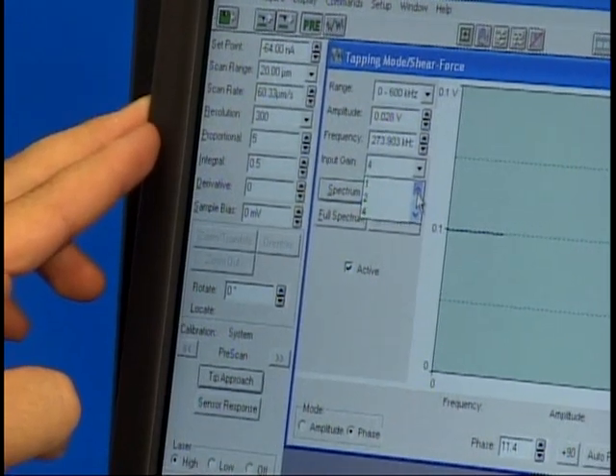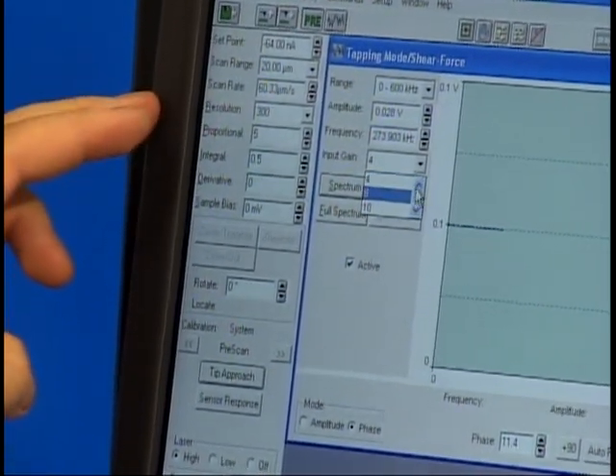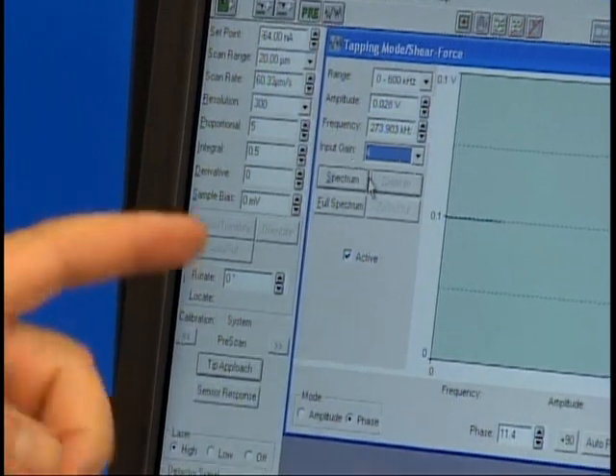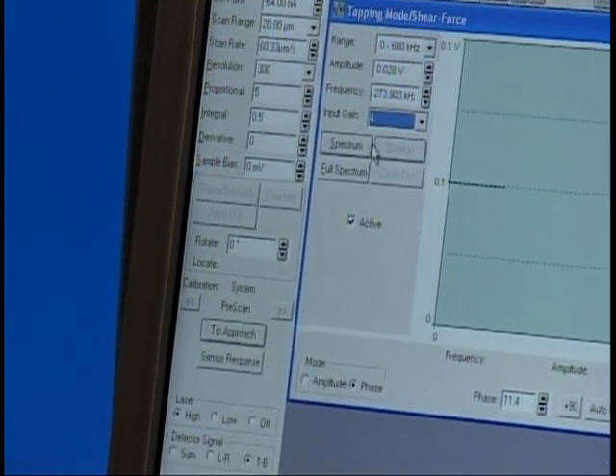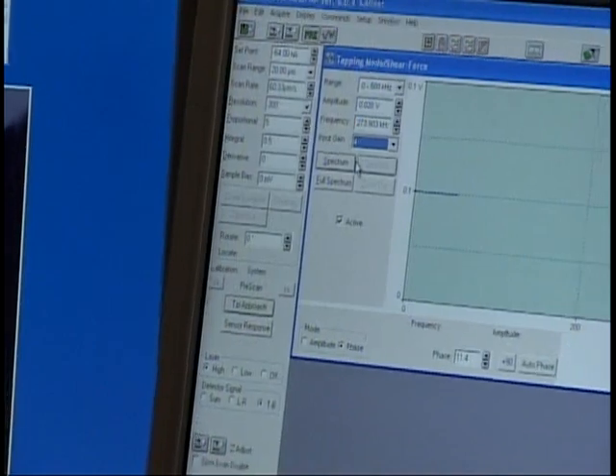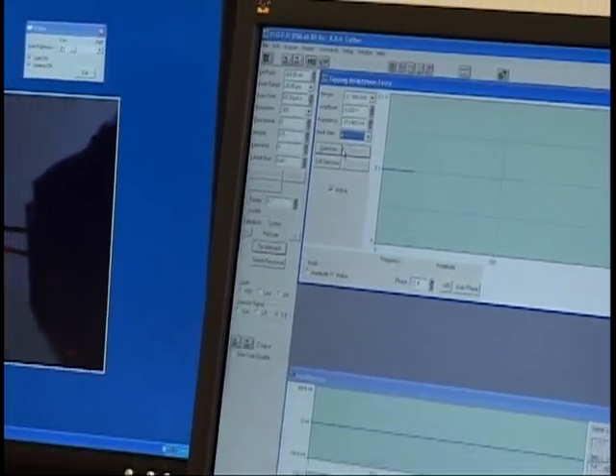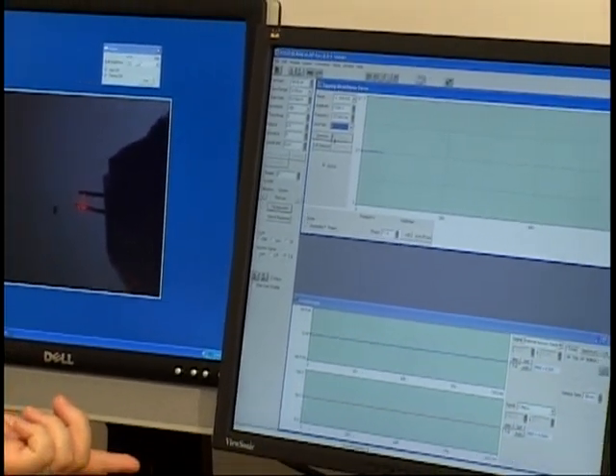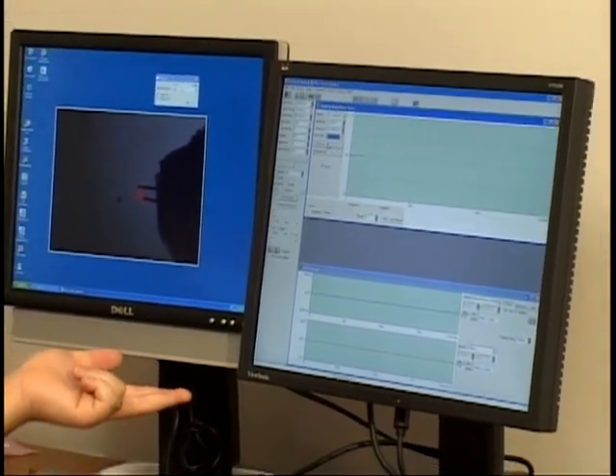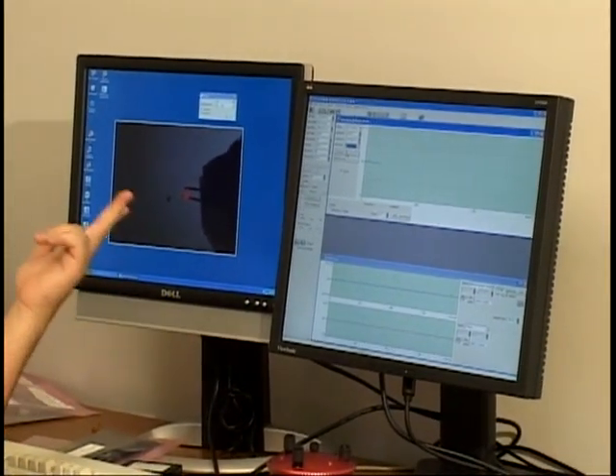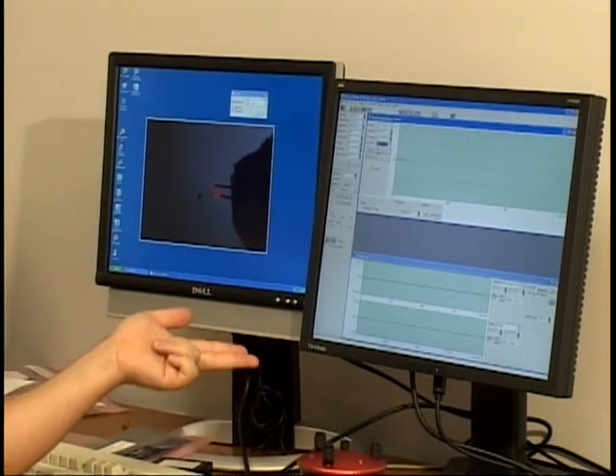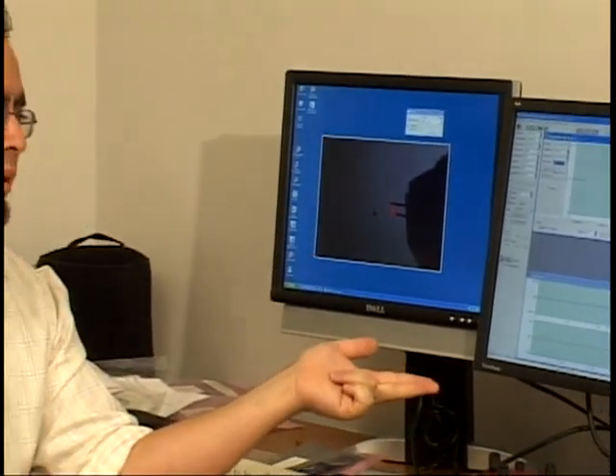400. You don't ever want to go that high. The highest you ever want to go is 8. An 8 input gain. If you can't get it with an 8 input gain, then you're probably not well aligned, or the probe might be damaged and it won't oscillate. And if you continually have problems with it not oscillating, maybe something's wrong with your Z scanner, or your Z scanner is not tapping, or you might have problems with the controller where the synthesizer board in your controller is no longer giving out a frequency sweep.